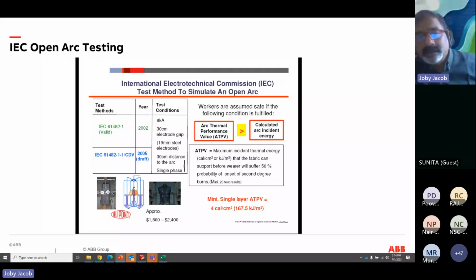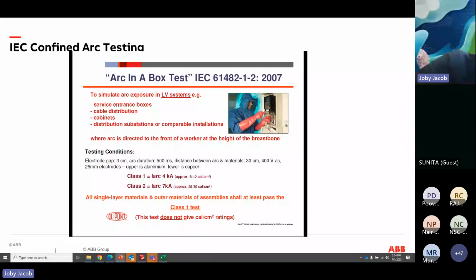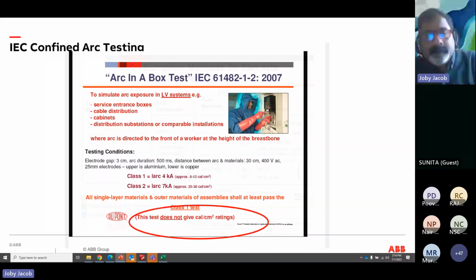Otherwise the clothing test is done by IEC 61482, what level of PPE and all those things. So it's like a mitigation level further to the engineering controls, and what level of PPE. So basically it is calculated on arc thermal performance value, ATPV, and calculated in terms of incident energy. So you get it in kilojoules, then it's converted to calories per centimeter square. Just for your information, to simulate, this is called an in-a-box test, when you are near to that. The standard is 61482-1 and 2.